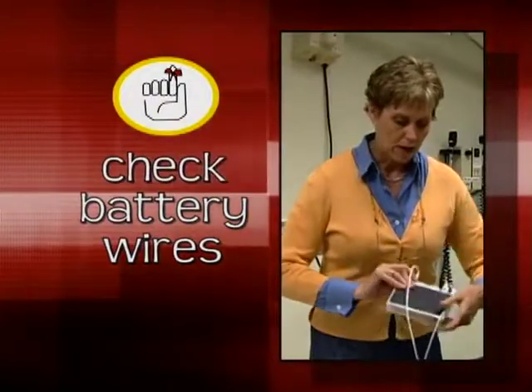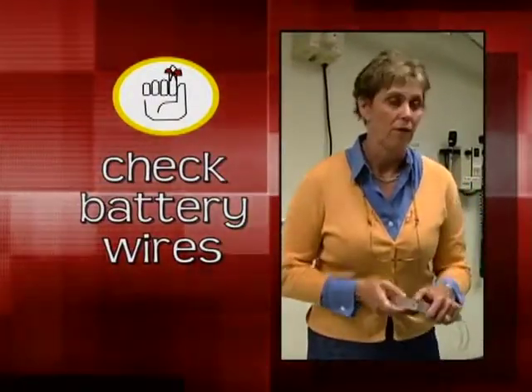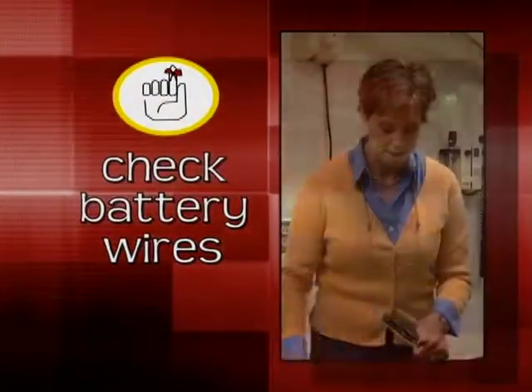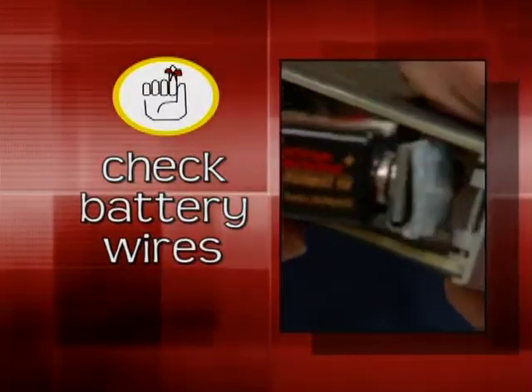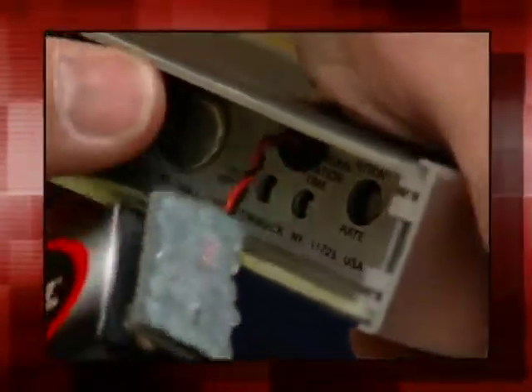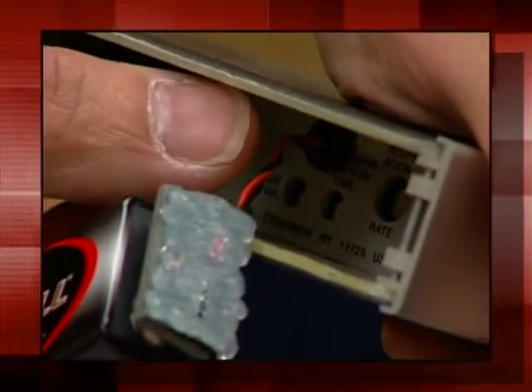And so what happens, and this is the most common form of failure with the device, is that the little wires inside there crack. They snap and break, and then the battery doesn't work. At that point, you do have to send the device to Avery to repair. If you have fresh batteries and the battery wires are okay, you would check the antenna.